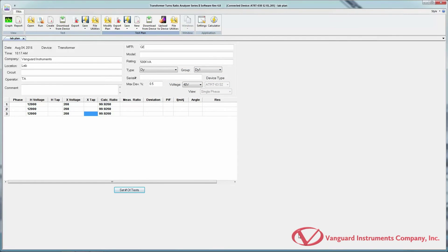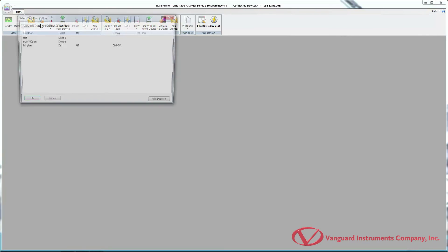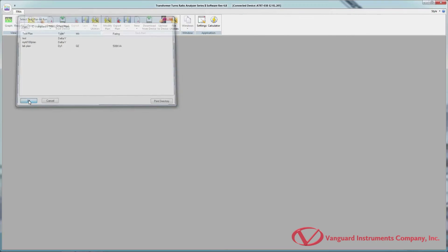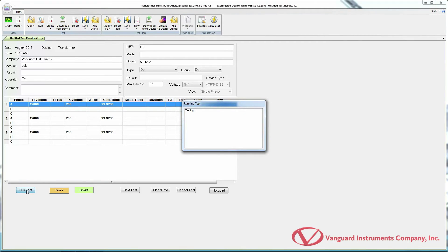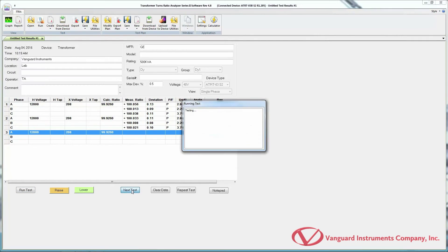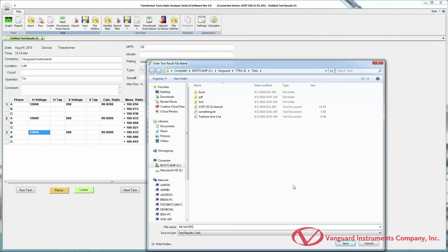Now we can perform a test using the test plan we just created. To run a test using a test plan, click on the Run icon in the Test command group. Select the test plan you'd like to use and click OK. The test plan will be loaded. Click on the first test and click Run Test. The connected ATRT-03-S2 will start performing the test on the transformer. Test results will be displayed once the test is done. Click Next Test to run the next test. Once all tests are done, click the arrow below Save in the Test command group and select Save As to save your test record.